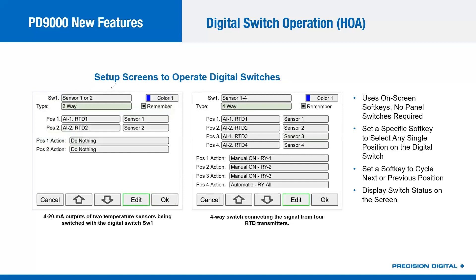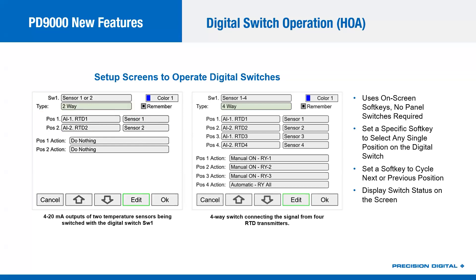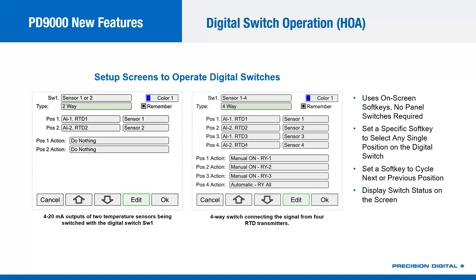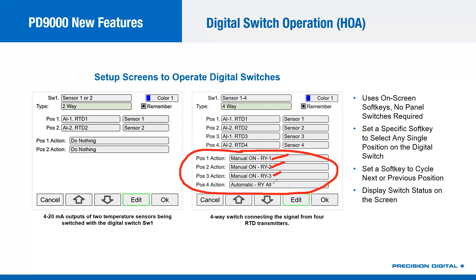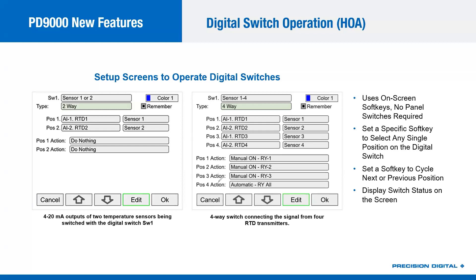For a two-way switch example, you can switch between two RTDs — sensor one and sensor two — so digital inputs or front-panel push buttons allow you to select which input reading to use. You feed the output of whichever sensor is currently active into other consolidator functions like PID control. You can do the same with four RTDs using a four-way switch, where each position selection turns on the appropriate indicator light on the panel or switches a relay back to automatic control.